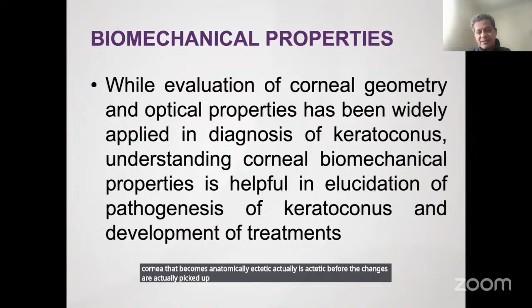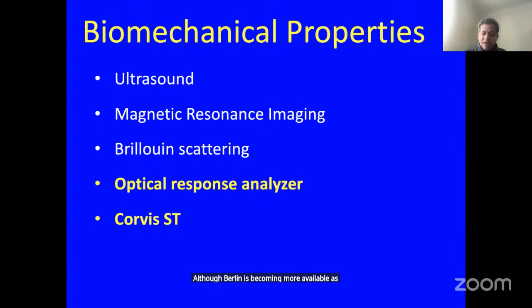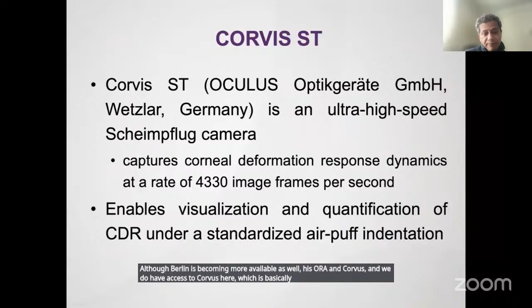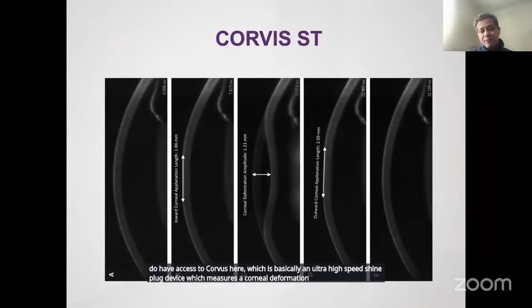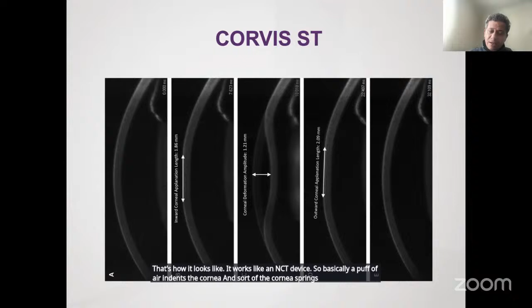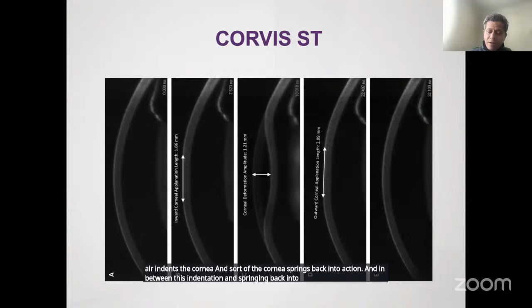So to measure biomechanical properties, the two devices that are commonly available, although Brillouin is becoming more available as well, are ORA and Corvis, and we do have access to Corvis here, which is basically an ultra high speed Scheimpflug device which measures a corneal deformation response to a puff of air. That's how it looks. It works like an NCT device. So basically a puff of air indents the cornea and the cornea springs back into position. And in between this indentation and springing back, thousands of measurements are made.